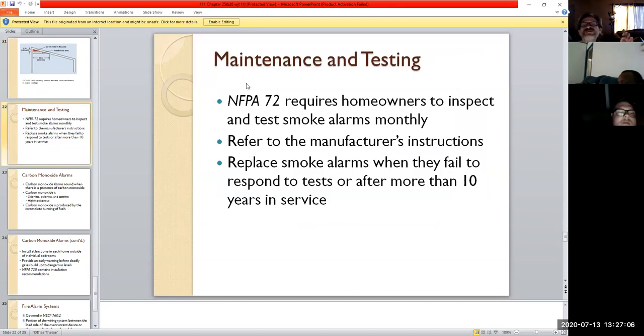And here we go. So what's our requirements? Well, NFPA 72 says that every month you're supposed to go through and look at the alarm and then push the test button, make sure it fires up okay, the battery's still good and that type of thing. You can refer to the manufacturer's instructions and make sure you're testing it correctly, that they have any special requirements or anything like that.